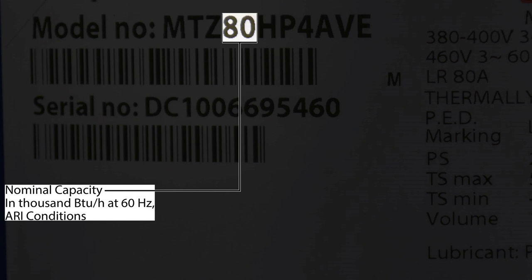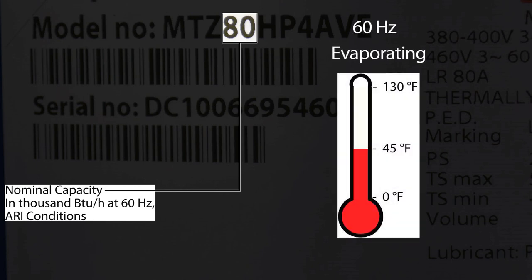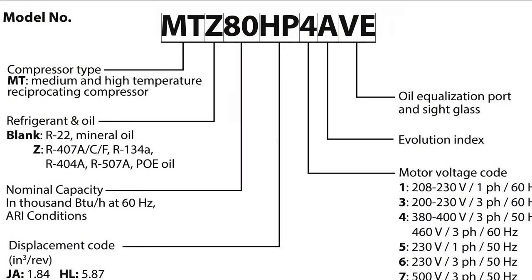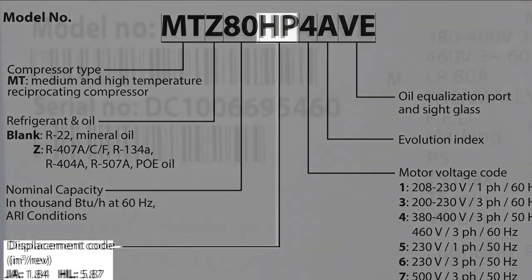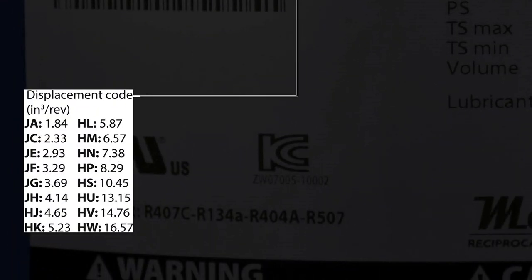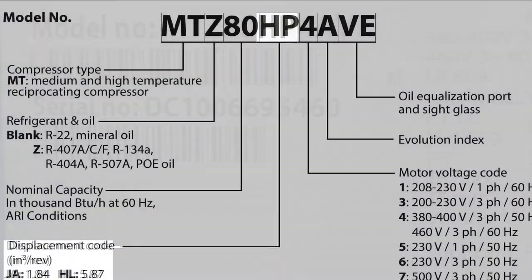The nominal capacity is determined using standard AHRI conditions at 60 Hz, with 45 degrees Fahrenheit for the evaporating temperature and 130 degrees Fahrenheit for the condensing temperature. The next two digits signify the displacement code, with units in cubic inches per revolution.